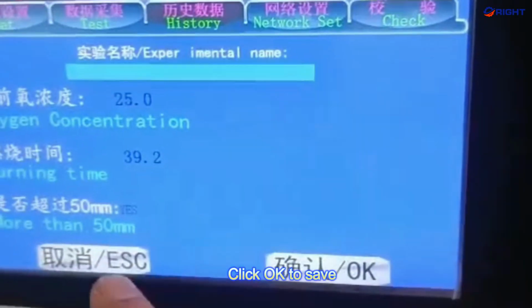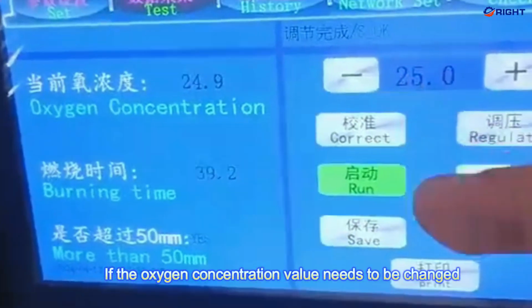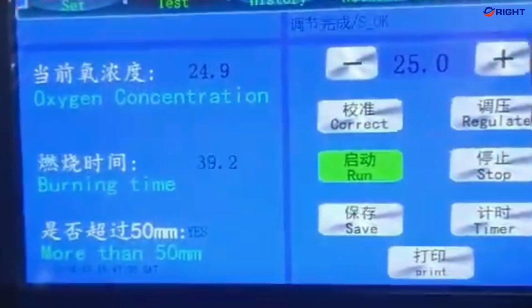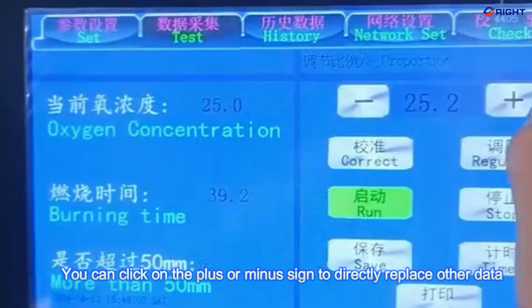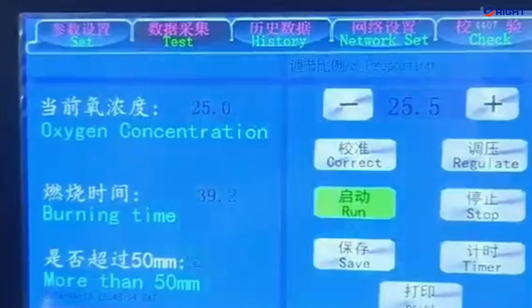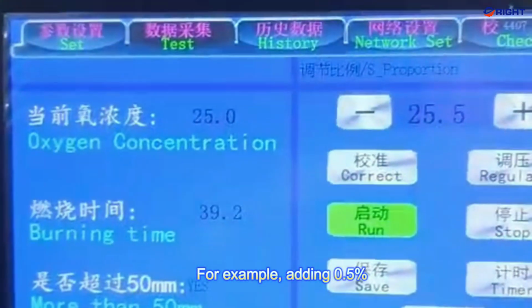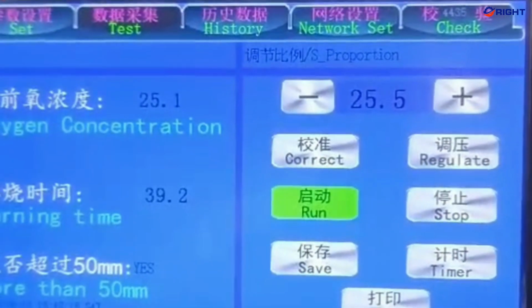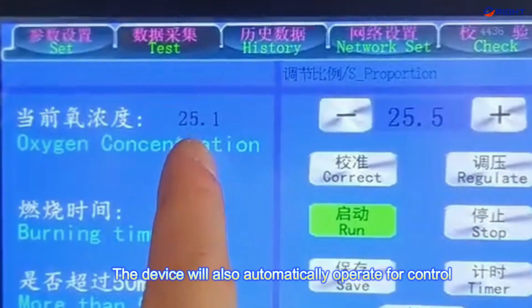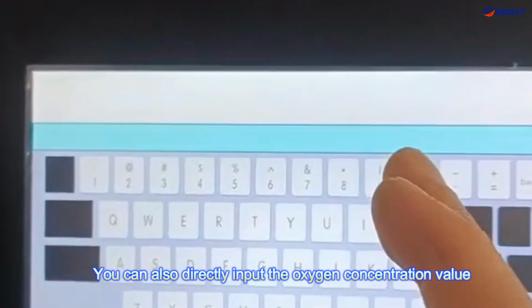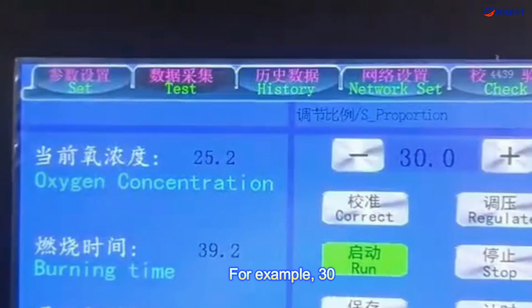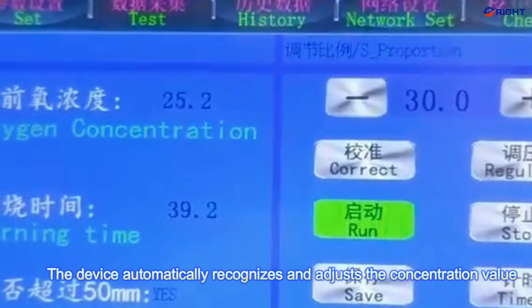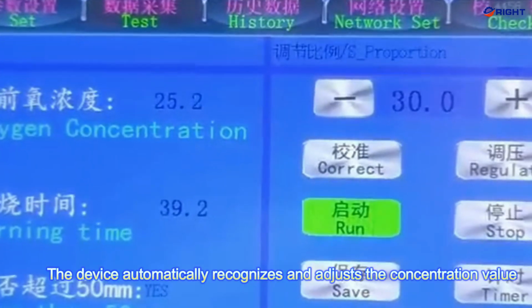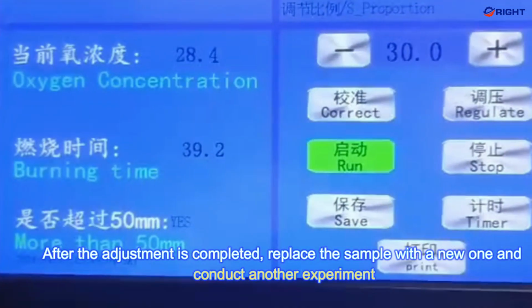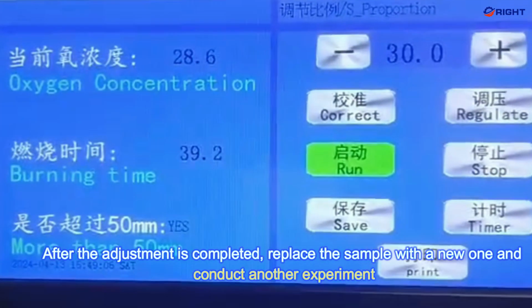Click OK to save. If the oxygen concentration value needs to be changed, you can click on the plus or minus sign to directly change it. For example, adding 0.5%. The device will also automatically operate for control. You can also directly input the oxygen concentration value, for example, 30. The device automatically recognizes and adjusts the concentration value. After the adjustment is completed, replace the sample with a new one and conduct another experiment.